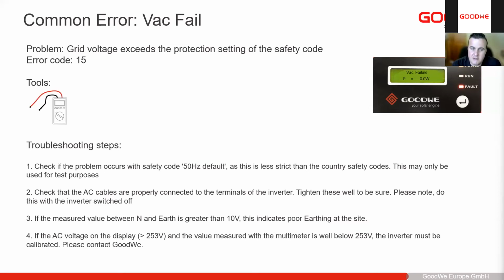We can check our AC cables, make sure they are properly connected. Sometimes a loose connection or hot connection can increase resistance on that cable, which means as soon as the inverter produces, the voltage will rise on the inverter, so you'll see a steady rise. And even if you set it to 50 Hz default, the voltage will rise past the safety of the inverter and it will go off again.